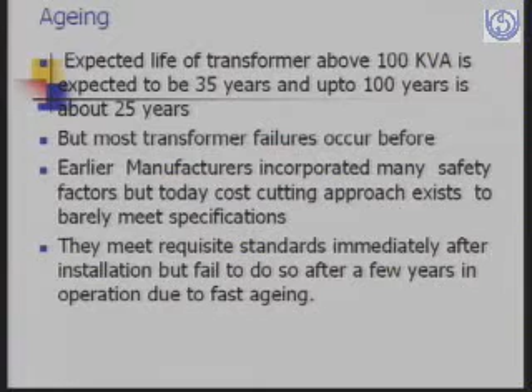We try to meet the specifications with the lowest cost, because in our tendering process we tend to buy from the lowest tender, ignoring the quality aspect. Even if we do have the quality aspect, the manufacturers manufacture it such that it meets the specifications in the beginning, but after 5 years the transformers fail because the safety factor has not been incorporated into the transformers. The transformers now are also being manufactured on a small scale.